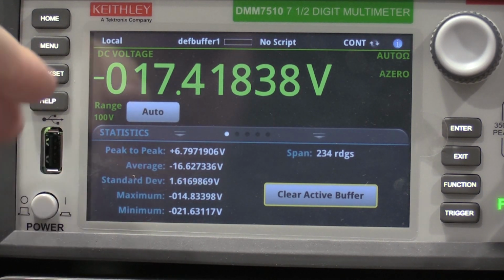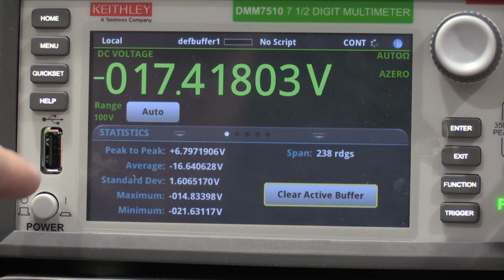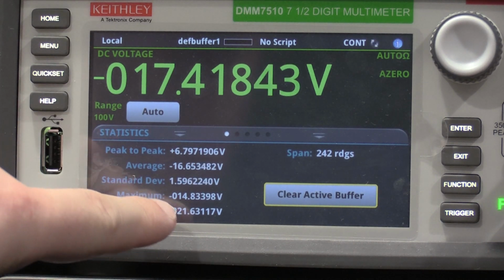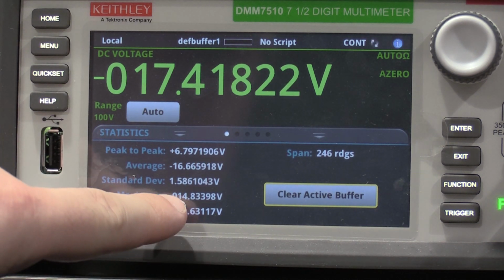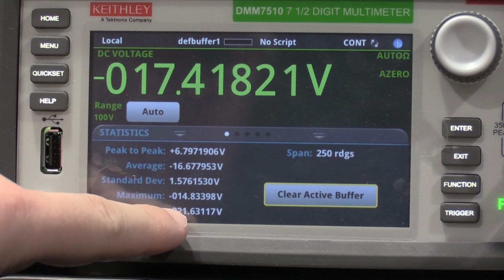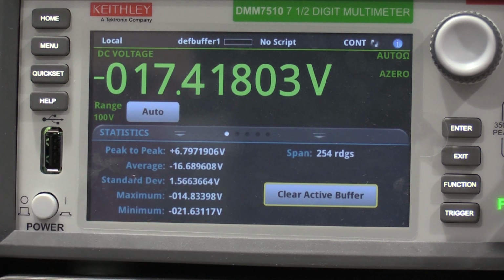I reset the statistics buffer as I was before I had started, and you can see our maximum was 14.83, minimum is 21.63, so that is absolutely perfect in what we're looking for. So that one is correct. We need to check the high side. So I'm going to wind it back up to the high side, and then I need to do the same thing.